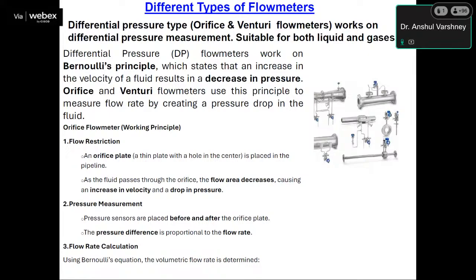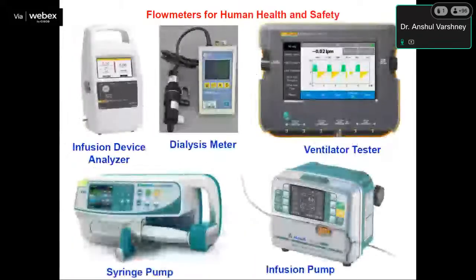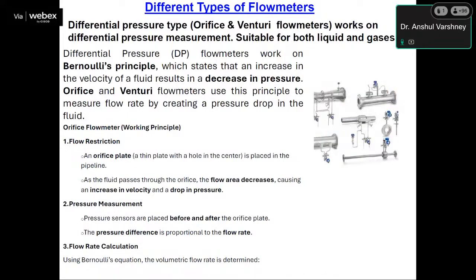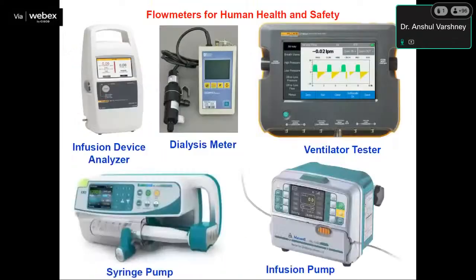If we consider the orifice flow meter, an orifice plate is placed in the pipeline. As the fluid passes through the orifice, the flow area decreases, causing an increase in velocity following the continuity equation, and a drop in pressure. Pressure sensors are placed at the upstream and downstream sides of the orifice plate. That pressure difference is measured, and it is proportional to the flow rate. So this type of flow meter uses Bernoulli's equation to calculate the flow rate.